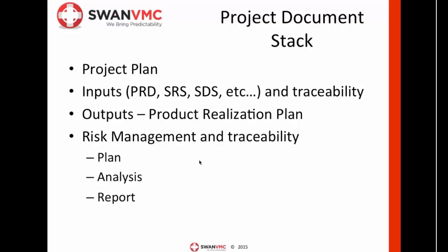You're going to have a systems document probably. If it's a software product, you're going to have an SRS, or a software requirement specification, and a software design specification and a system architecture document. Likely, some of the people that I've dealt with, and a really common way to do this, is to break it down by subsystem and roll it up into an overall systems document. Often they're broken down by disciplines. The 62304 requirement really is a different way of doing the development process that's specific to medical device software, so oftentimes people want to break that out separately.